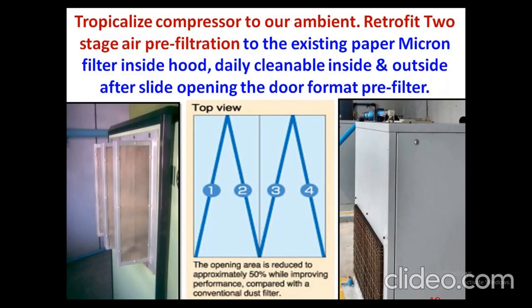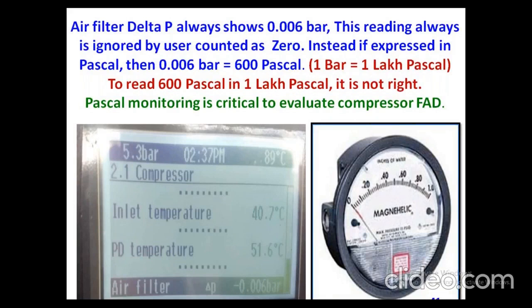Automatically you can achieve an excellent FAD, free air delivered, at the compressor air intake, and you can save around 3 to 5%. Some mills have lost more than 10% because of choke in the paper filter affecting the FAD. This is a mandatory provision to be done on any textile mill air compressor. You have to educate them. The OEMs give it for the safety of the compressor, but they also have to educate the textile mill to improve energy savings in compressed air generation. Any mill can operate from 150 watts per CFM to 250 watts per CFM. Many of the mills are still operating at 250 watts per CFM. That is the SEC. But now the mills have started operating at 150 watts per CFM. That is what we have to target and achieve for the given mill.